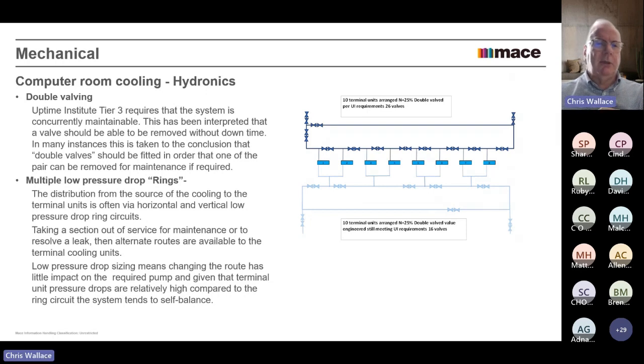Anyway, that's that. The other thing just on hydronics is most of the data centers that we see use ring mains for the distribution. Oversized, low pressure drop ring circuits, and they might have a horizontal and a vertical. Depending on where your terminal equipment is, you typically have a horizontal circuit, and then vertical circuits feeding the different floors. The whole idea of this is you can take a section of the ring main out to resolve a leak, and you've got alternative routes available.